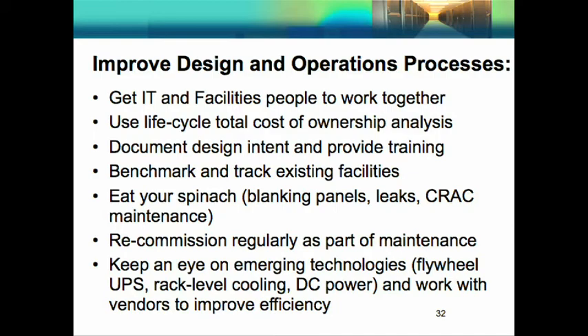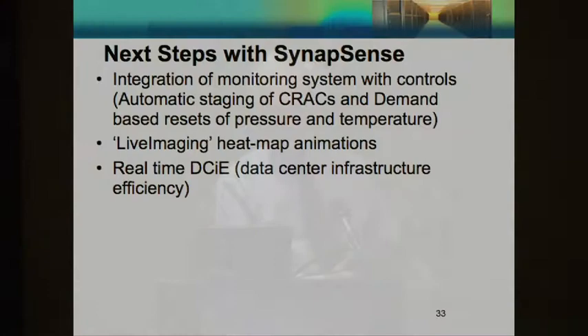Our next steps with SynapSense are to integrate the monitoring system with controls, because right now we can watch but can't turn CRAC units off — leaving more on than we need and causing them to run less efficiently. We're also implementing the live imaging system that looked like a CFD model but was real life, installing real-time DCIE monitoring so we can see the impact of any change we make, and retrofitting the CRAC units with VAV.